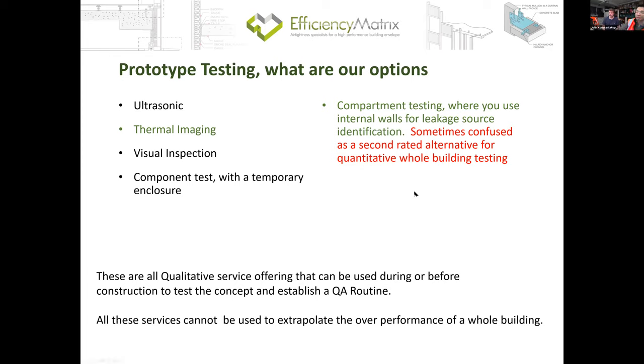What are the common systems or common methods that we can use? Our ultrasonic testing is extremely effective for systems like curtain wall, doors, and windows, but it's not as effective in multi-layer construction like timber or metal stud wall constructions. The other method is, if some kind of enclosure can be created, we can pressurize that room or that floor and then do thermal imaging or smoke testing to identify the weak points, to confirm the sealing specification in the cable tray or duct penetrations is good enough.